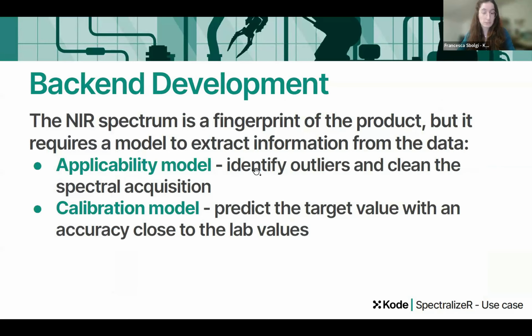The first is an applicability domain model that has the purpose of identifying outliers and cleaning the spectral acquisition. So without human supervision, we can take the whole spectral acquisition and clean out the spectra that are not useful for the analysis, maybe because there is not enough sample on the conveyor belt, or because of any other problems. The applicability domain understands if the spectra we are reading are compatible with the ones we used to calibrate the model. Once the spectra are filtered, we can use the calibration model to actually predict the target value and deliver it to the operator.